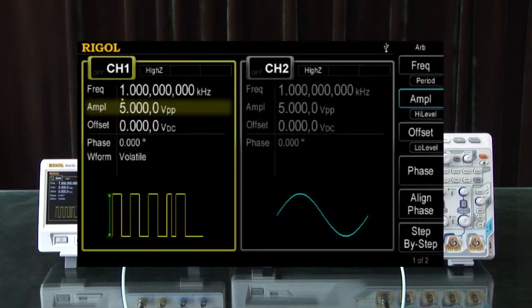As the picture shows, there is an arbitrary waveform with different pulse widths. We can use pulse trigger to isolate a pulse based on its time duration and trigger on it in a stable and repeatable way.